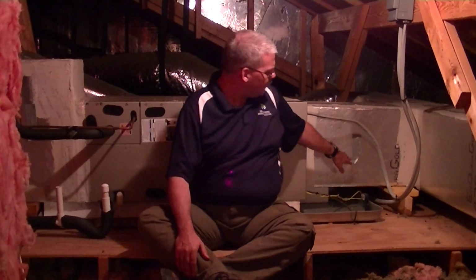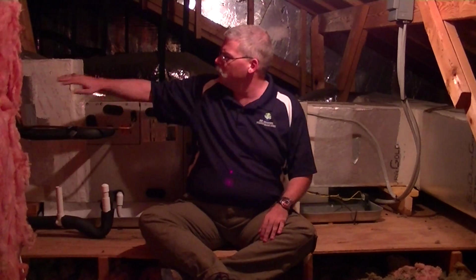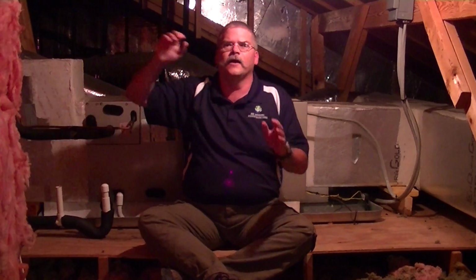So the HVAC contractor has provided us with a hole here in the supply plenum covered with duct tape, and a hole over here covered up with duct tape as well in the return plenum. Always use the holes provided for you by the HVAC contractor, and if the HVAC contractor has not provided those holes for you, please contact them and ask them to make holes for you in order for you to do the total external static pressure test. The values that we're looking for need to be within 0.05 inches of water column. That's our range of tolerance from what the HVAC contractor measured and what you measure.